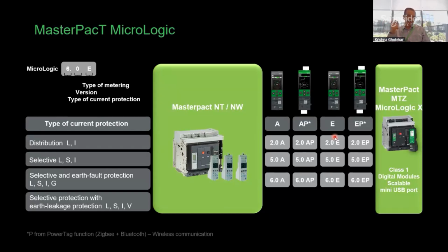So all the trip units have the maintenance indicator. As a reminder, in the existing range of NT and NW, you have to go to MicroLogic P to have those maintenance indicators. Along with that, communication protocols and others are standard features. Now, on top of that, continuing our legacy of innovations in MasterPact range of circuit breakers, in MTZ Active, what we are bringing new to the market, of course, with the new trip units, is the world's first wireless sensor or wireless communication circuit breaker in the market.